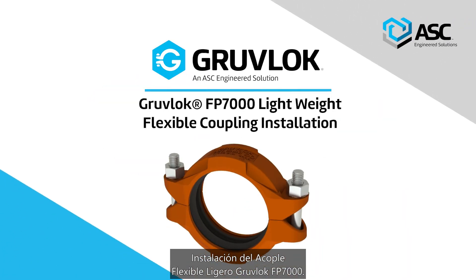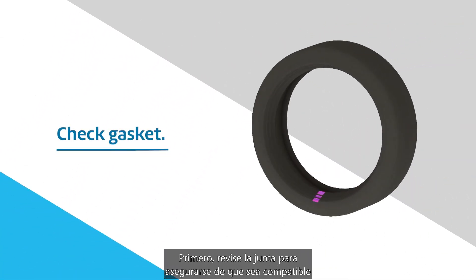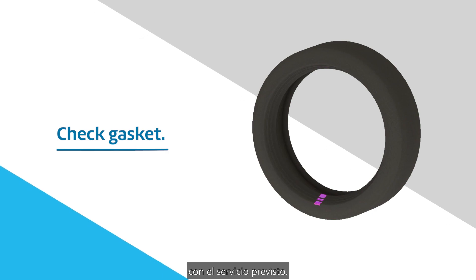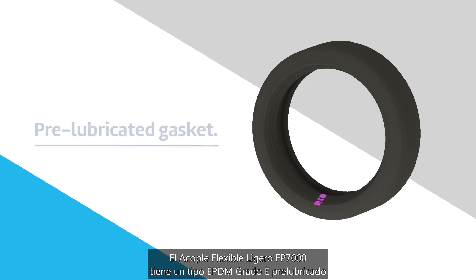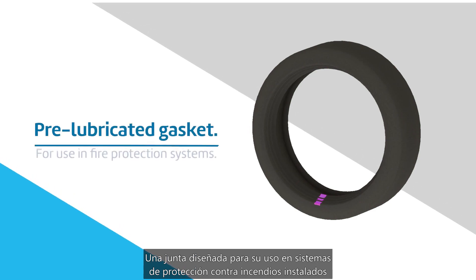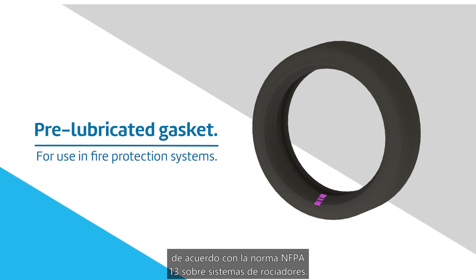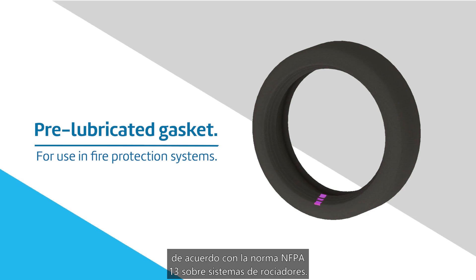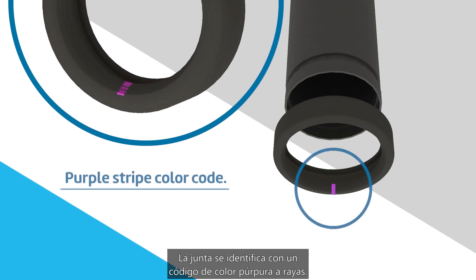Gruvlok FP7000 Lightweight Flexible Coupling Installation. First, check the gasket to confirm it is compatible for the intended service. The FP7000 Lightweight Flexible Coupling has a pre-lubricated Grade E EPDM Type A gasket, intended for use in fire protection systems installed in accordance with NFPA 13 standard sprinkler systems. The gasket is identified by a purple stripe color code.